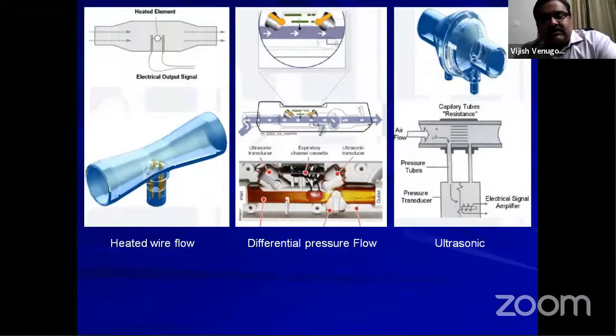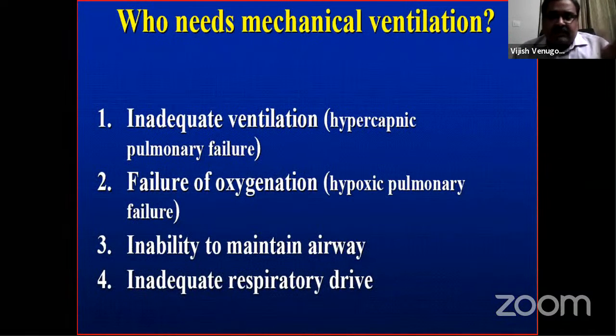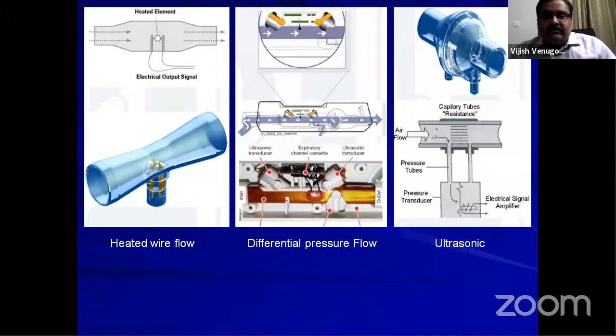The last one is the sensors, or the flow sensors, which will give you the feedback. So there are many different types. The common ones are the heated wire flow sensor, the one shown on the left. Okay, there's a small mistake. The one in the center is the ultrasonic one, and the one on the right hand side is the differential pressure flow sensor. What it does is it will measure the flow that is going and give you an output. So that is briefly regarding the anatomy of a ventilator. What will you see? What are the different parts of the ventilator?